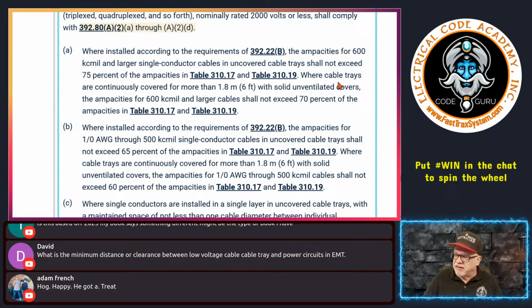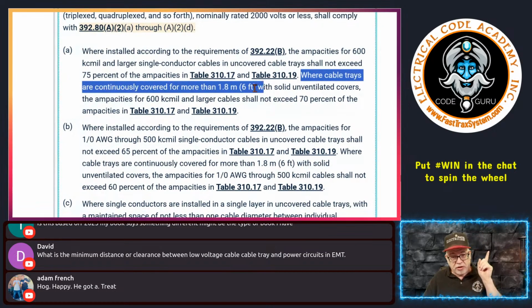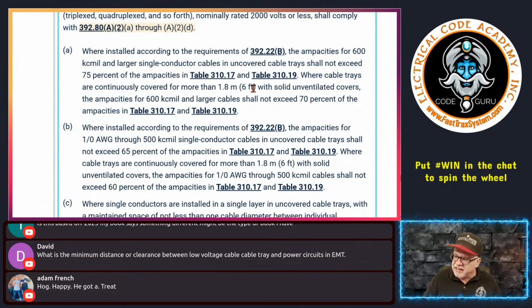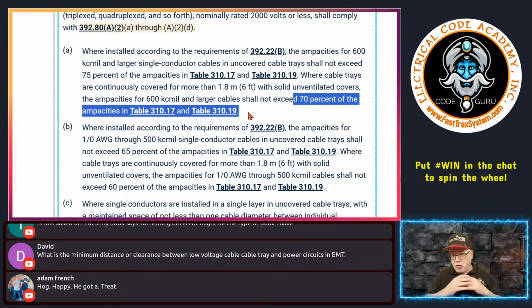So there's that. Now it says where cable trays are continuously covered for more than 6 feet, that looks very familiar, right? Then it says with a solid unventilated cover, the ampacities for 600 kcmil and larger shall not exceed 70% of the ampacity in those tables. So if you're doing 6 feet or more, then guess what? Now you're going to have a problem. You're going to be saying, well, wait a minute, now I can't exceed 70% of whatever the ampacity is. So go to Table 310.17, take the ampacity, and take 70% of that. And you can't exceed that value.